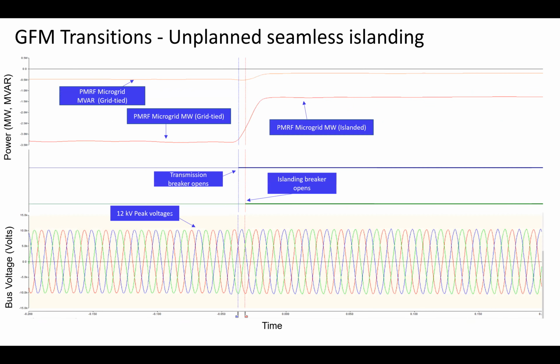So the third transition here is an unplanned seamless islanding, which is more complicated than a planned islanding sequence. What we've done here is try to replicate a test where we start in normal operation, dispatching to the KIUC grid per dispatch set points that we receive. There could be a fault on the grid that could trigger protection opening. The negative means that's power going into the grid, so we're dispatching about 3.3 megawatts here, grid connected. And what KIUC did was they opened a transmission breaker, which transfer tripped the islanding breaker. And you can see those commands being initiated here.